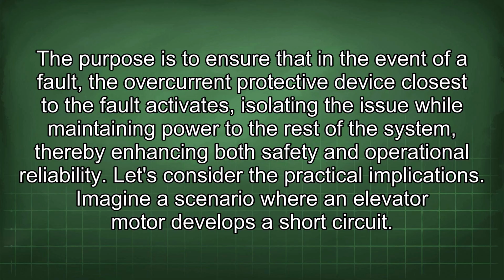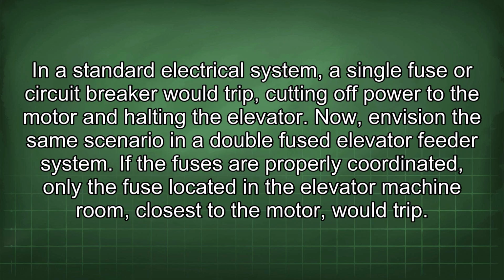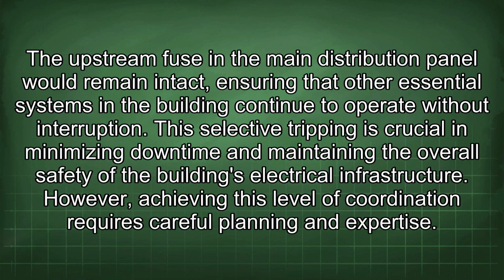Let's consider the practical implications. Imagine a scenario where an elevator motor develops a short circuit. In a standard electrical system, a single fuse or circuit breaker would trip, cutting off power to the motor and halting the elevator. Now envision the same scenario in a double-fused elevator feeder system. If the fuses are properly coordinated, only the fuse located in the elevator machine room closest to the motor would trip. The upstream fuse in the main distribution panel would remain intact, ensuring that other essential systems in the building continue to operate without interruption. This selective tripping is crucial in minimizing downtime and maintaining the overall safety of the building's electrical infrastructure.